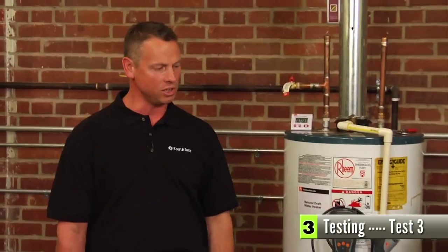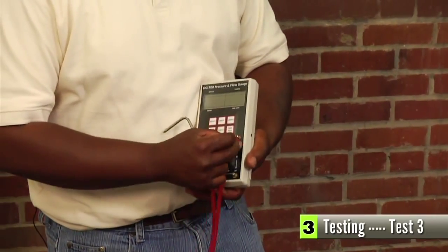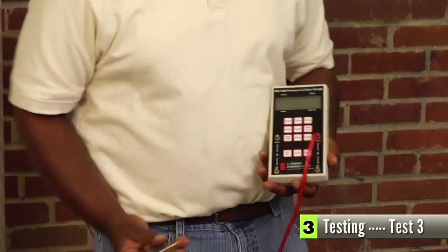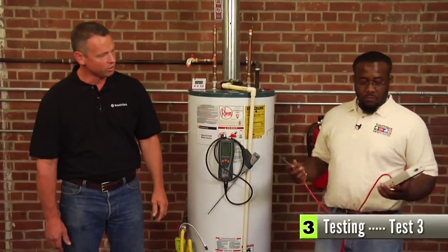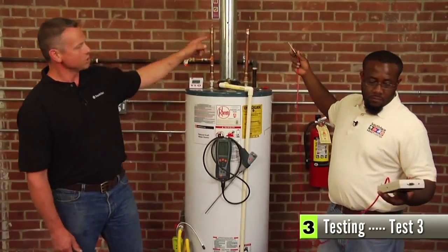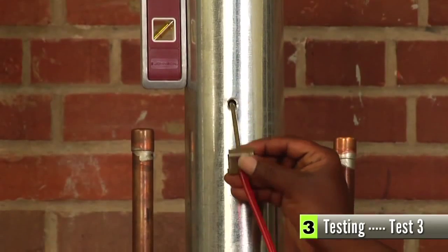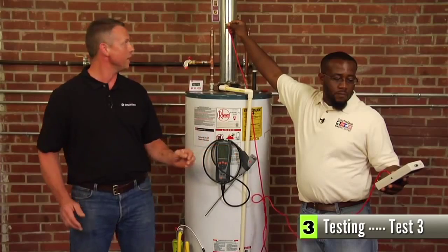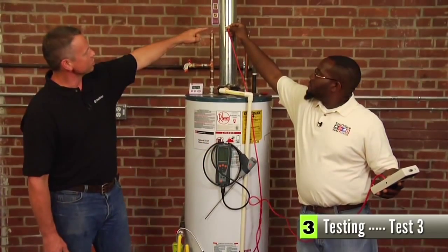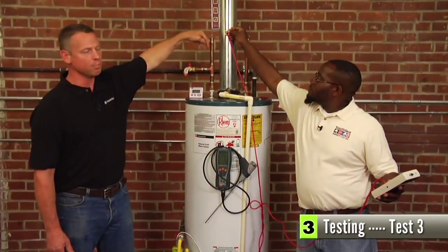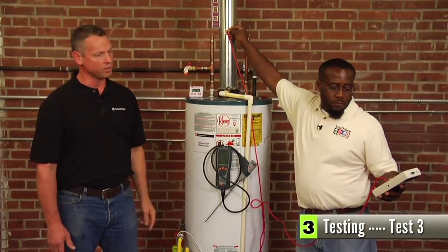So Benson, will you hook up the DG700 and let's measure the pressure inside that flue. Okay, with our DG700, we're measuring flue pressure as our input with reference to the CAS. So you see the flue pressure is the input, and the reference tap is open to the CAS. And we've got the static pressure probe in the center of the flue pipe facing down. Benson, what's the pressure inside that flue? The pressure inside the flue is -1.7.